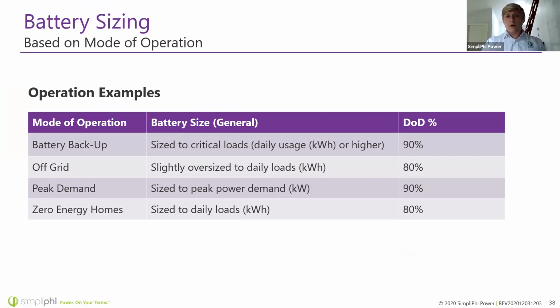If you're off-grid, when sizing you want to look at the mode of operation. Since you're cycling these batteries daily, I'd recommend 80% depth of discharge, which gives the longest lifespan. So when sizing your system, this battery has 3.8 kilowatt hours of storage if you really need it, but on a daily basis you'll try to use about 3 kilowatt hours, which is about 80%.